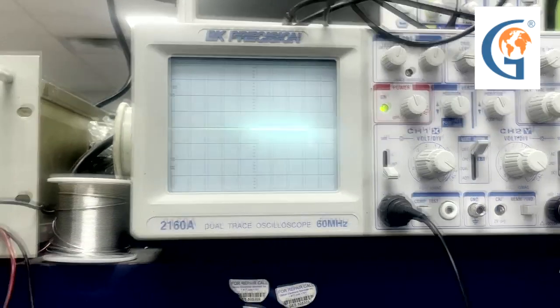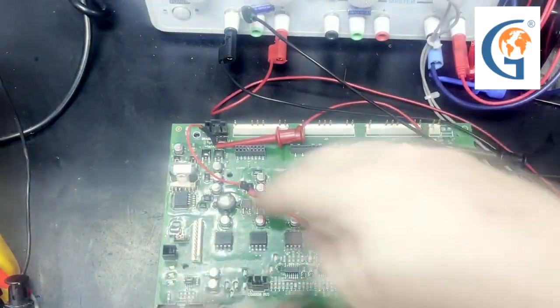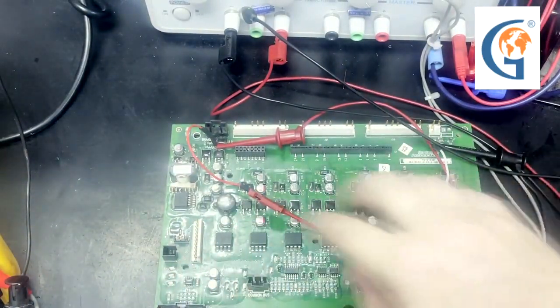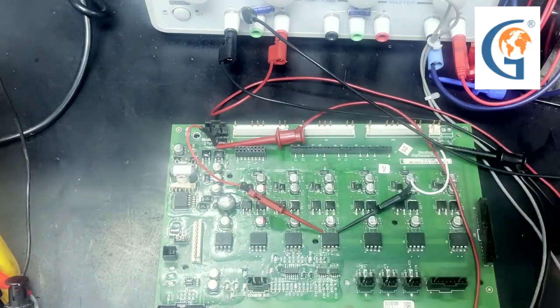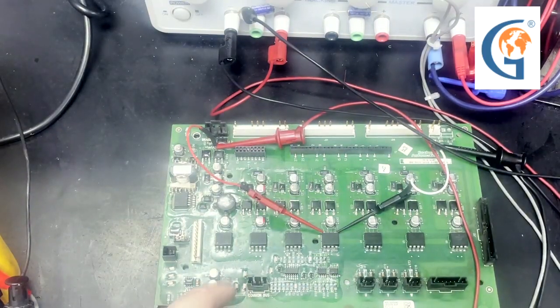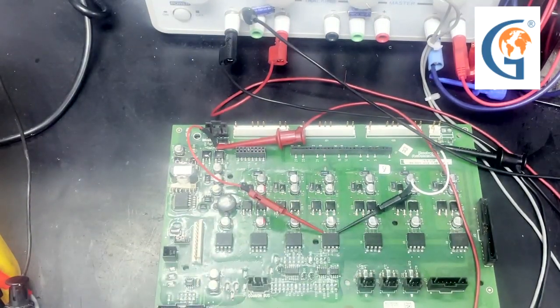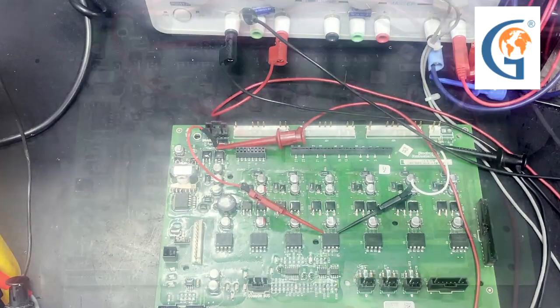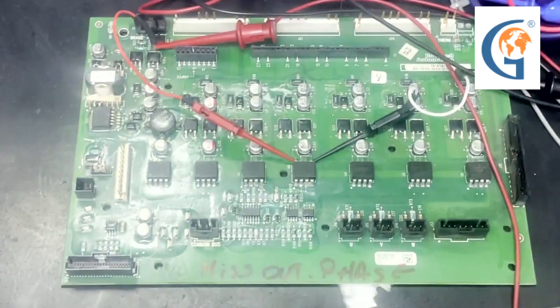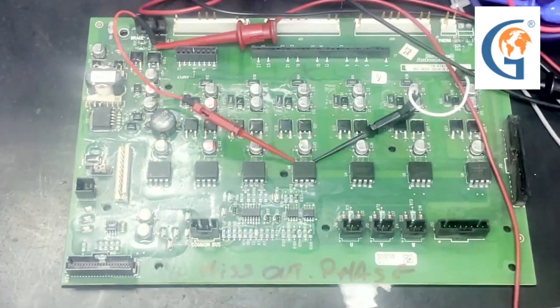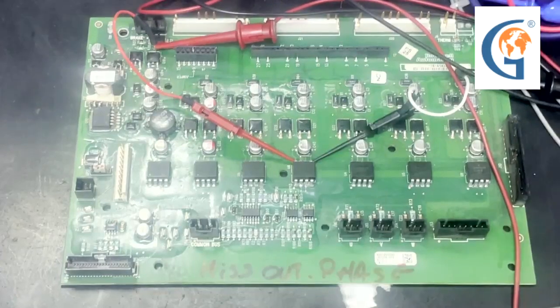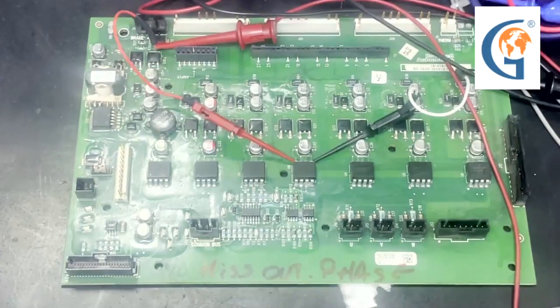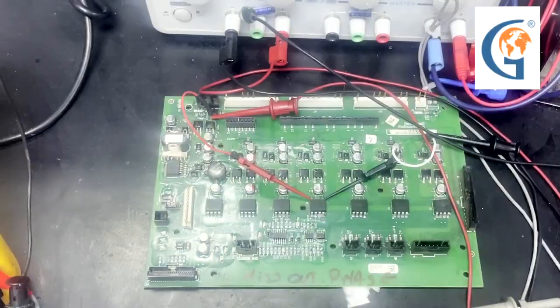We will continue to check all these optocouplers, do capacitance and ESR checks on the capacitors, and check the diodes and the connections. Once any bad components are replaced, we will check this board in the drive and make sure it's running properly, and get the customer back up and running.